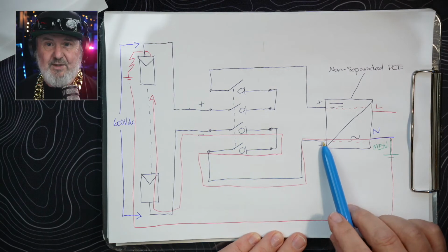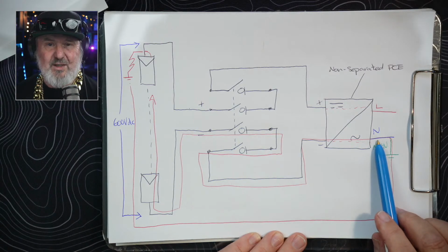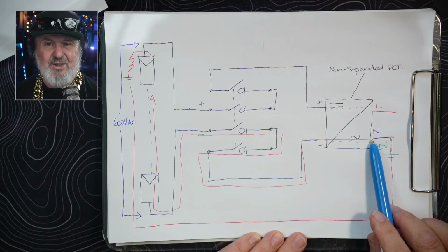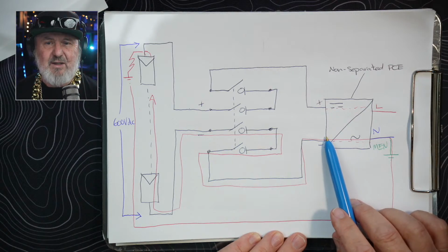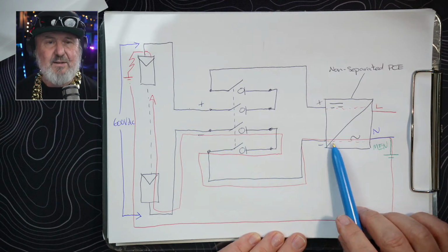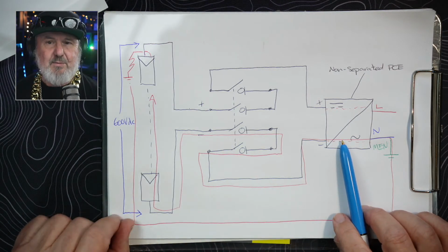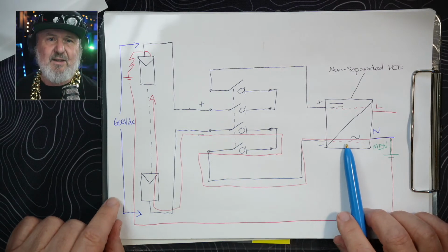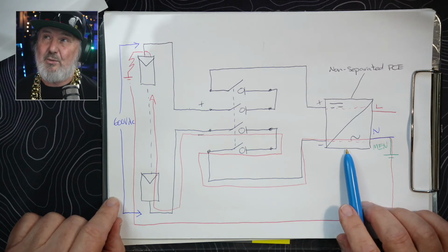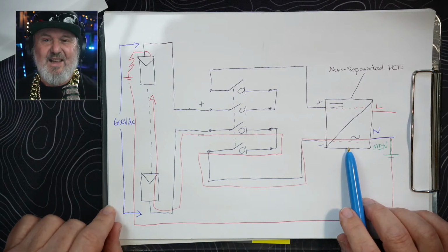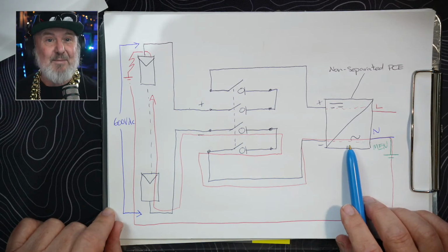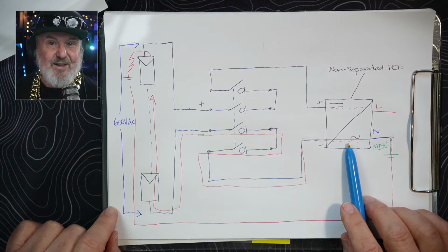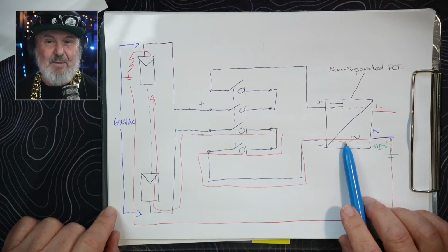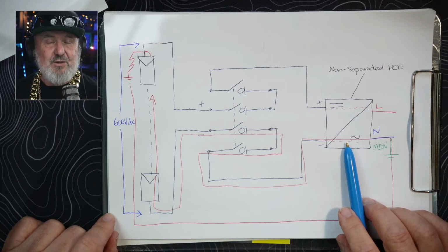It's fully dead. Once this fault occurs, most inverters cannot sustain a direct bolted fault on the DC side. In fact, inverters are required to meet a test under IEC 62109 parts 1 or 2. I can't remember which one it is. And it's 300 milliamps of leakage to earth. Not 9 amps or whatever the array can put out. So it's a very small amount of leakage the inverter must be able to interrupt and shut down safely.